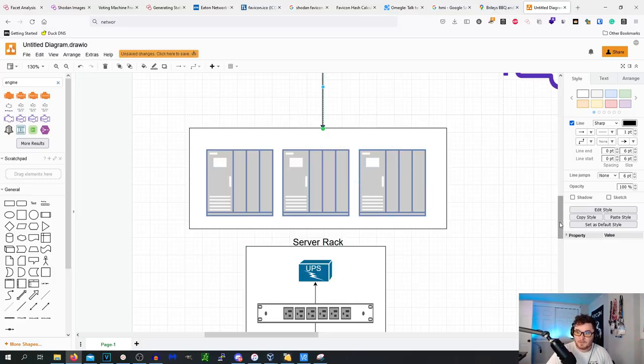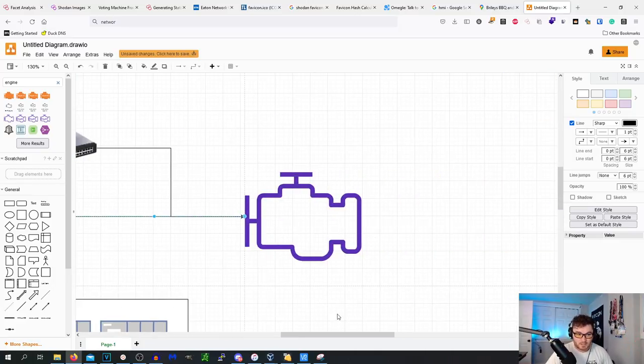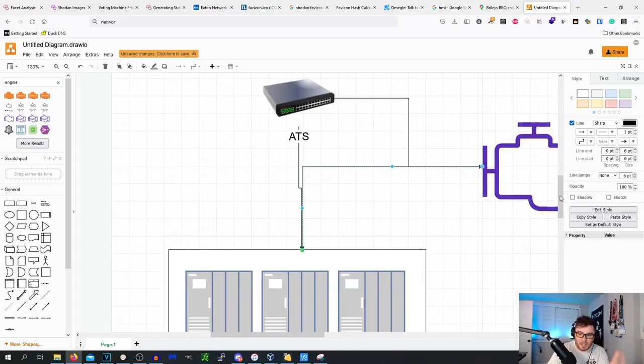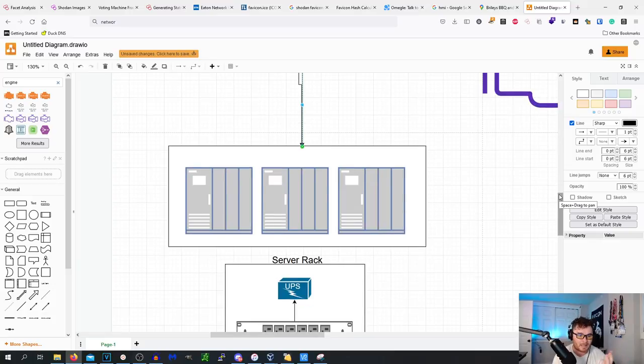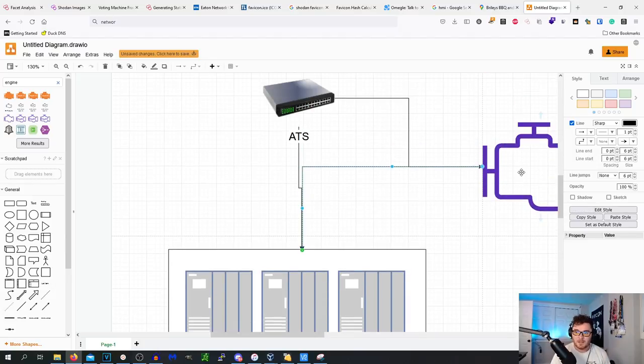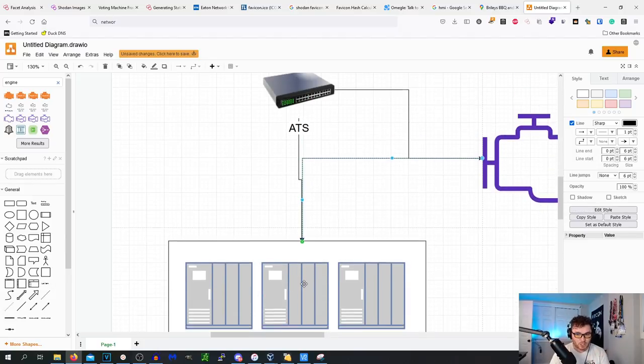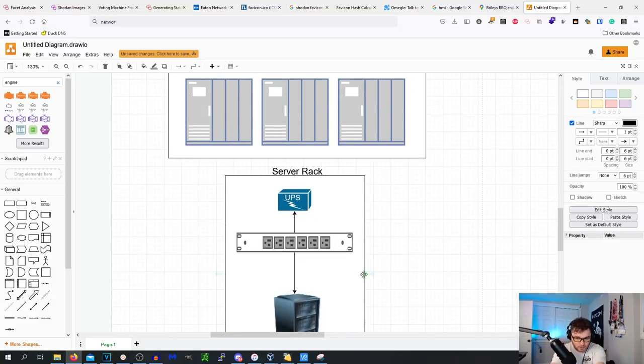While that's happening, it triggers the diesel generator on site to kick on. That takes some time to spin up. It has a glow plug in it, and it takes a little time to get to capacity where it can support an entire data center. While that's going on, the batteries, at the places I've worked at, could support the data center for about 30 minutes. Once the generator is at capacity, it feeds down this way, charges the batteries, and then you get into the server rack.